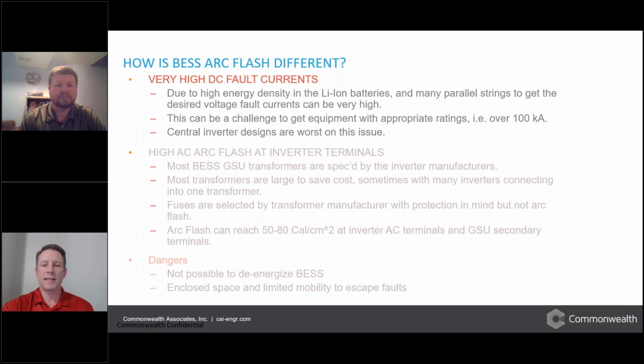If anybody's worked on AC short circuit calculations, anything over say 30 to 50 kA is considered extreme. We've seen over 150 kA. So it's hard to get the equipment that's rated that high, and a lot of the time we have to negotiate with manufacturers to get them to rate them higher than they've ever tested them before. If we have a central inverter where a lot of strings are hooked up to one large inverter instead of a bunch of small inverters, that makes it significantly worse too.